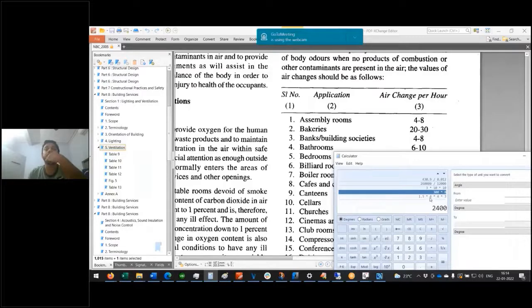That's where I'm saying, if you want to ensure this 72 cubic meter per minute, if I multiply it by 60, you need at least 4320 cubic meter per hour. This is only 2400. So your exhaust and supply fans should be designed to cater to 4320 cubic meter per hour. Did you get my point? For minimum fresh air, you need 2400 cubic meter per hour, but to ensure thermal comfort, we need 4320 cubic meter per hour. Including the openings? Yeah, including the openings.